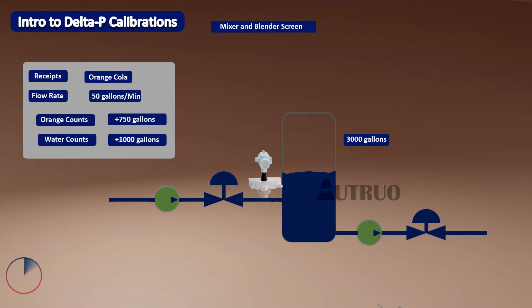Examples: to stop the process pump and close the inlet valves. But in situations where there are malfunctions, the required volume might not be attained or might be exceeded. This error depends on the state of the transmitter. So basically, in situations where the transmitter is not accurate, we might either have less or more fluid during blending and mixing of process products. This is one of the contributing factors that can affect the quality of the product produced.